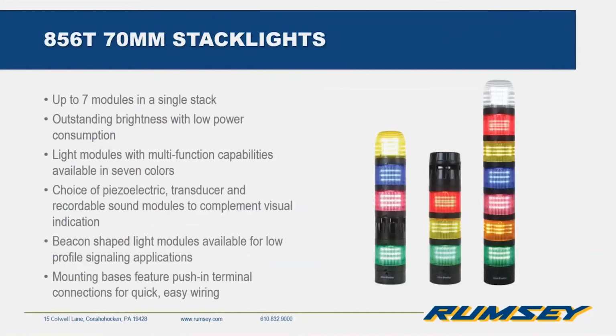And finally, we have the 70 millimeter stack light option. These have been out for a little bit, but they're starting to pick up a little bit more steam. You can have up to 7 modules in a stack, and they're all LED. They have really high lumen output per watt, so they're really efficient. And you can really create these in any configuration you want. You can buy them as components or as pre-assembled units. And they also have sounders, which can either be top mounted or inline. And there are various mounting base options as well.